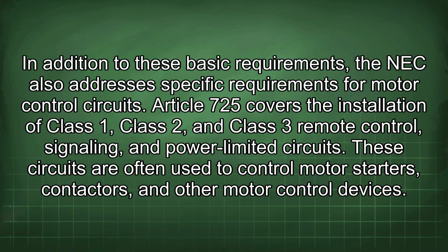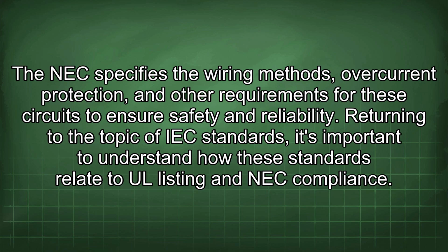In addition to these basic requirements, the NEC also addresses specific requirements for motor control circuits. Article 725 covers the installation of Class 1, Class 2, and Class 3 remote control, signaling, and power limited circuits. These circuits are often used to control motor starters, contactors, and other motor control devices. The NEC specifies the wiring methods, overcurrent protection, and other requirements for these circuits to ensure safety and reliability.